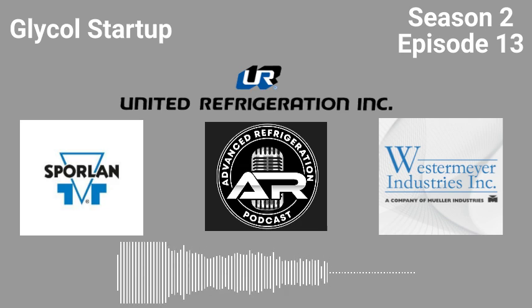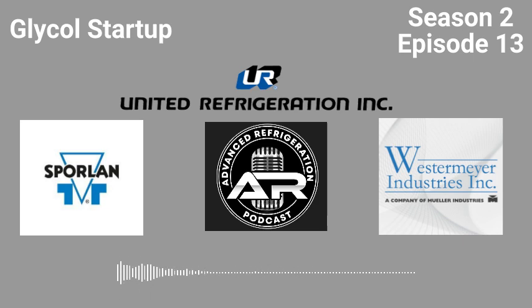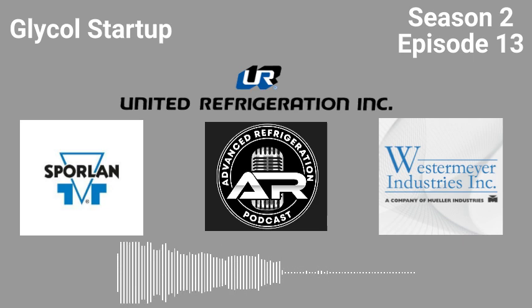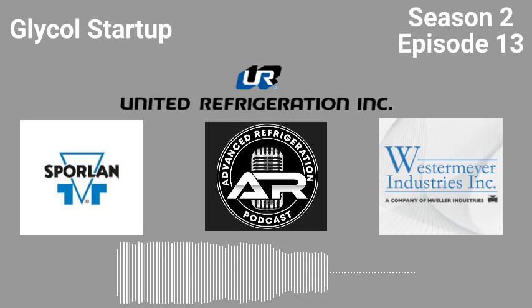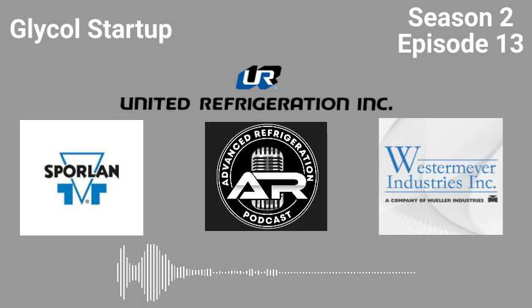So the other thing I want to talk about, we've had this situation come up quite a bit here lately, at the last 5 stores I've been involved with. Zero Zone, I won't mention the customer, but Zero Zone has had a giant rash of warm fluid heat exchangers crack. I know of at least 14 stores where this has happened, all across the country, over the last couple of years. So it's not like a brand new heat exchanger issue. It's not a manufacturing issue. This is a Zero Zone issue.